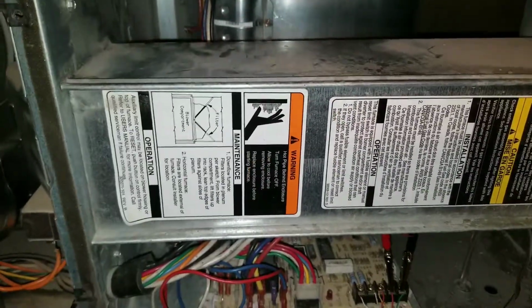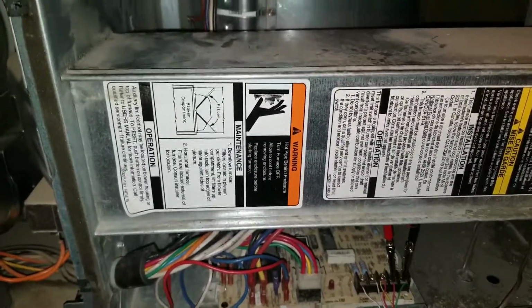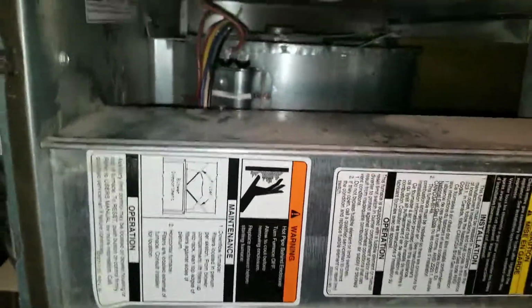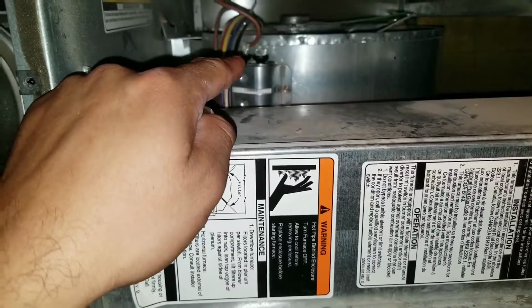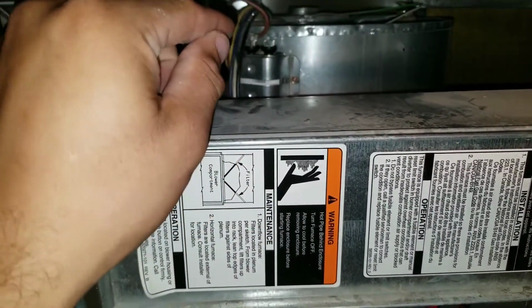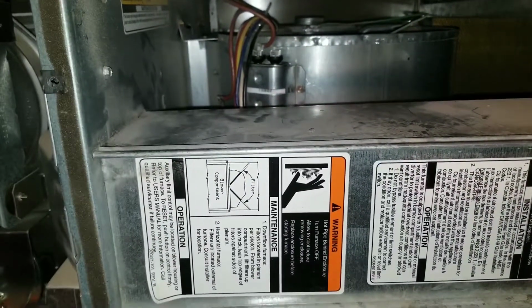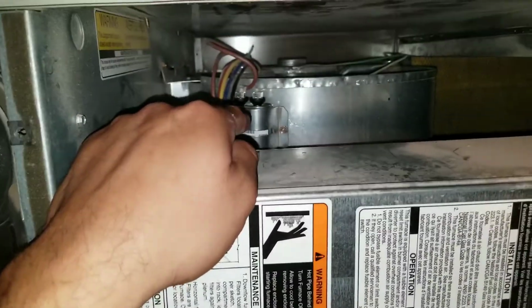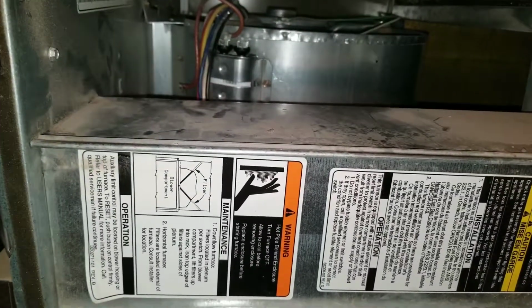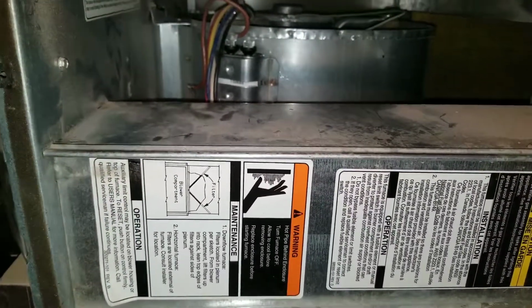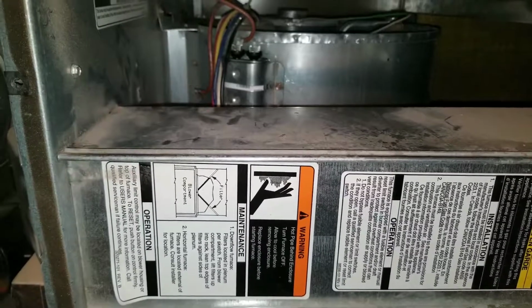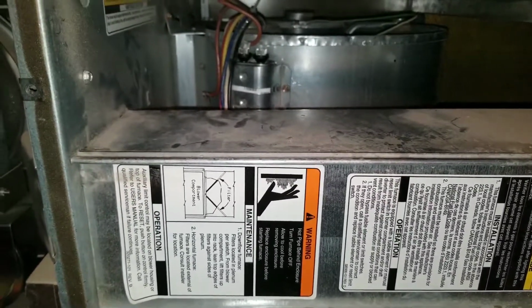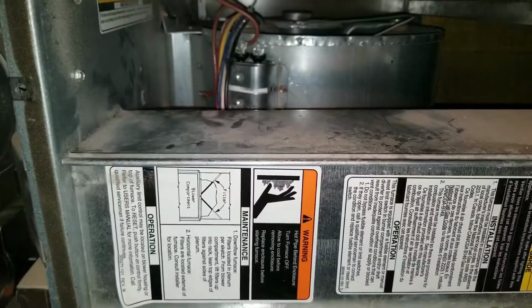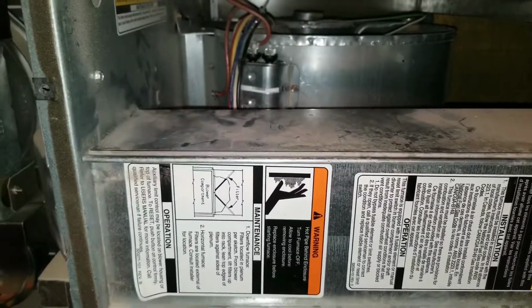Now the reason this is beneficial is because right now we're going to troubleshoot our blower motor. Here I removed one of my leads for my blower motor going to the capacitor. This means that my capacitor is not energizing my blower motor, so it's almost acting as if we have a blown capacitor right now. What I would do if I received a call that the AC wasn't working, and I pressed in my contactor, my compressor turns on, my fan motor turns on, I would obviously come to the thermostat and make sure that it's in the on position.